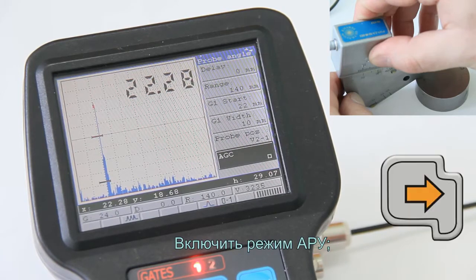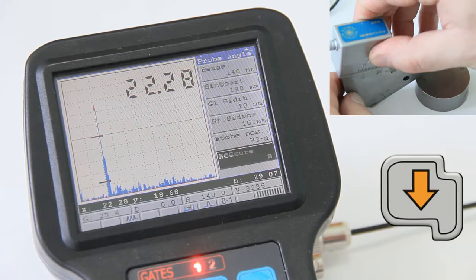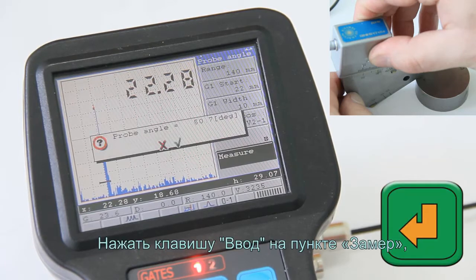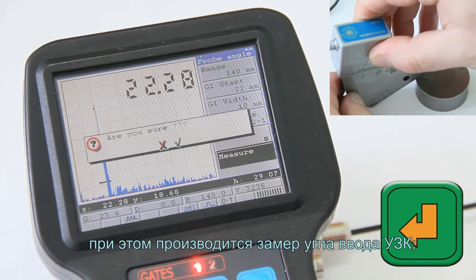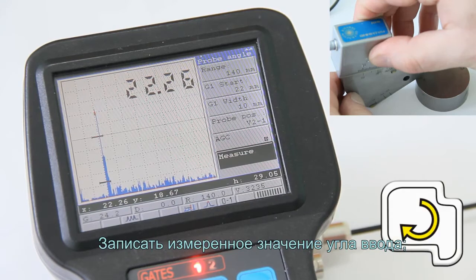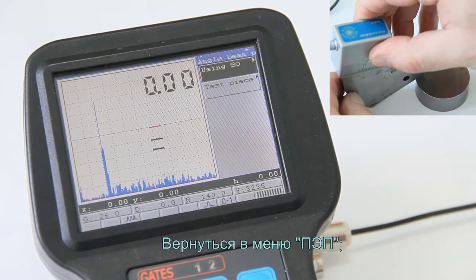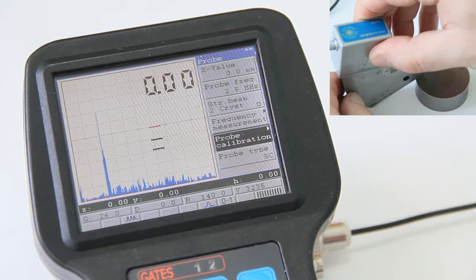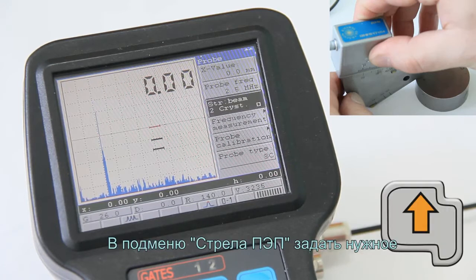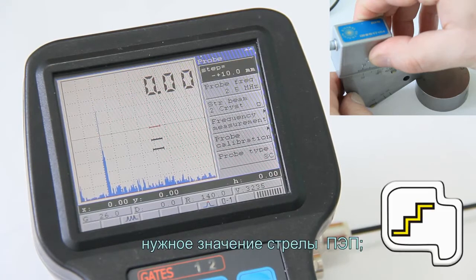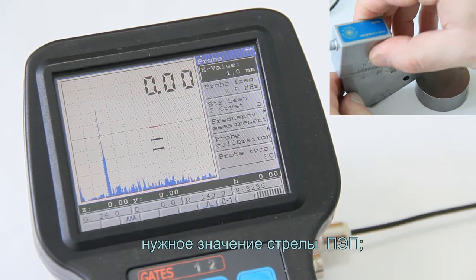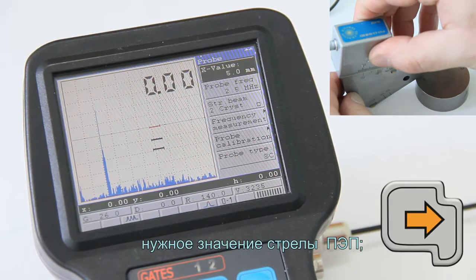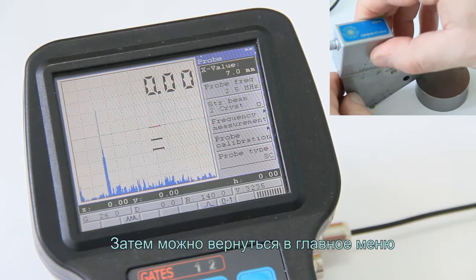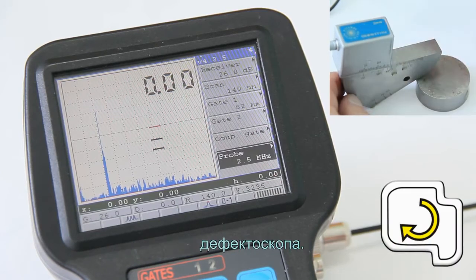Switch on the AGC mode. Press Enter key in Measure menu item to measure the probe angle. Save the measured probe angle value. Return to Probe menu. In X value submenu, set up the measured X value. Then you can return to the main menu of the flaw detector.